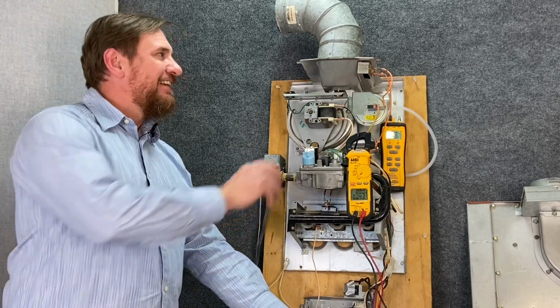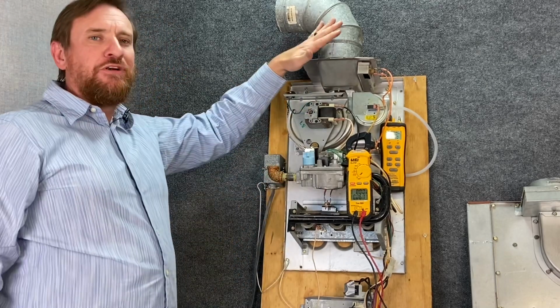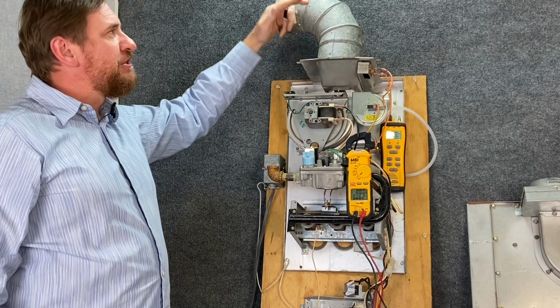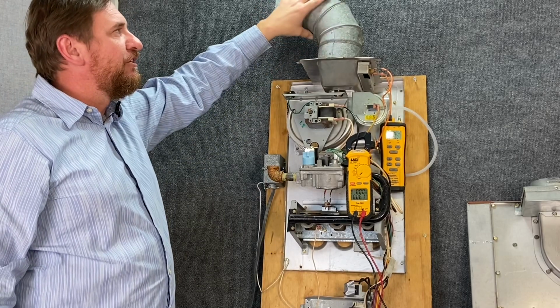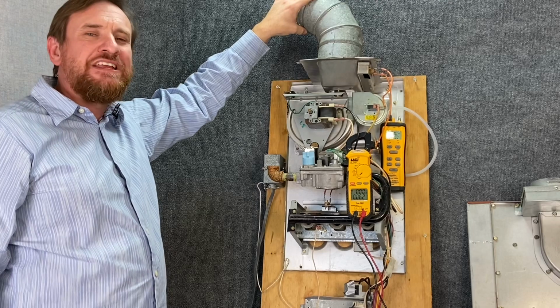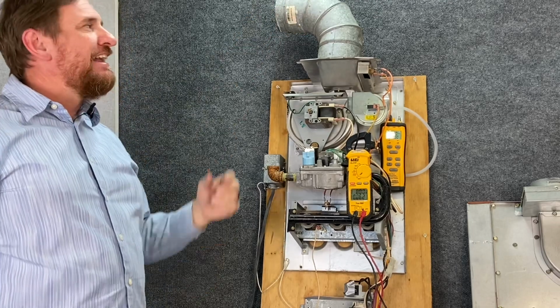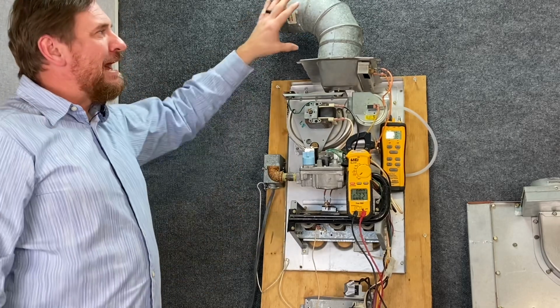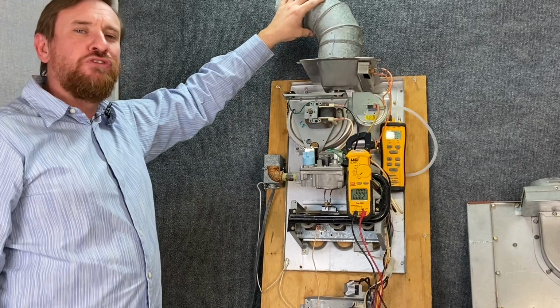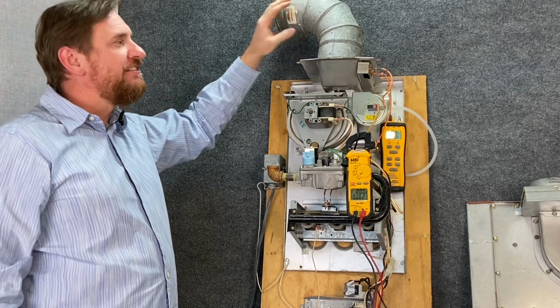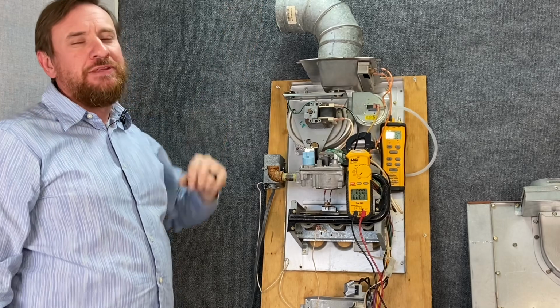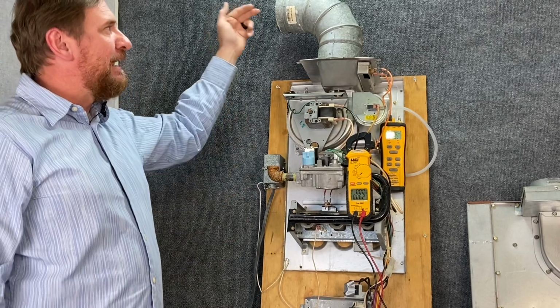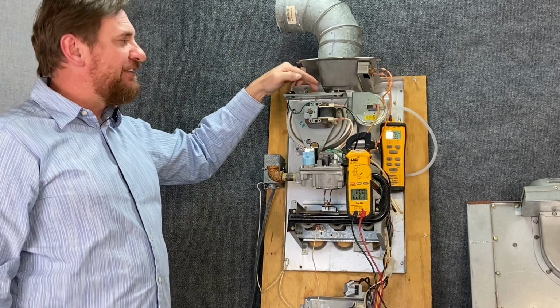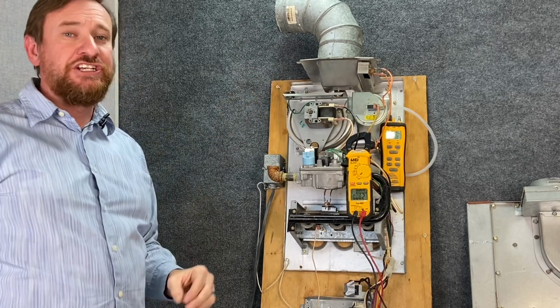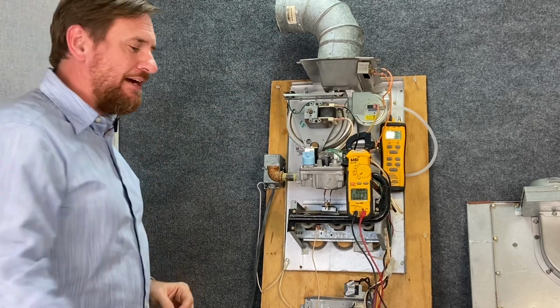So if it's a vent pipe like this, it's very important we note that. I've also seen customers take and put heat exchanger material on their vent pipe to try to get extra heat out of their furnace. It sounds like a good idea. What happens is they cool this vent pipe too much. That causes condensation to happen because we drop the temperature below dew point, and that comes back and rusts out our flue pipe, rusts out our motor, as well as rusts out our heat exchanger. These are things that are very important to keep in mind.